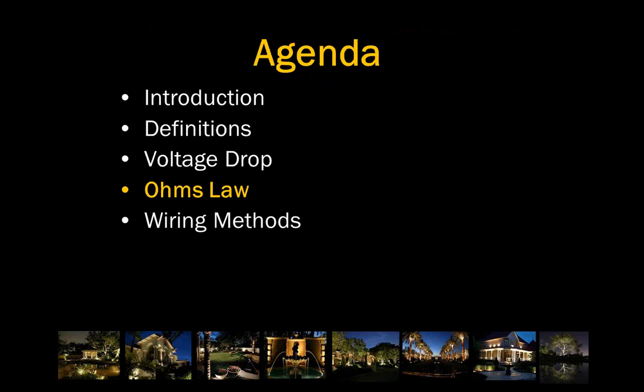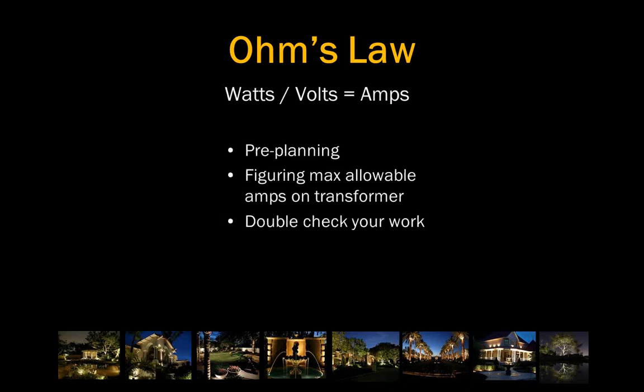Let's take a step into Ohm's law here and talk about how that helps us with voltage drop. So Ohm's law states watts divided by volts equals amps. Now, I use this on every project that I design. As I get the fixtures all laid out and I start figuring out where my wires are going to go, I start running Ohm's law. This helps me with my wire size, my wire length, and my transformer sizing.